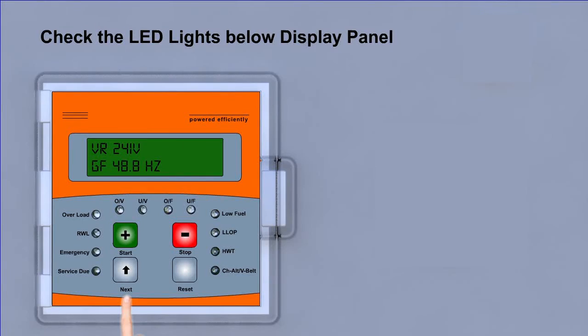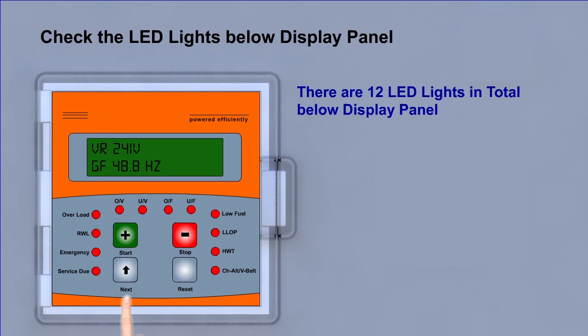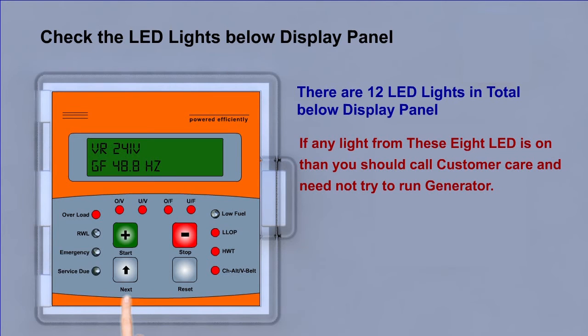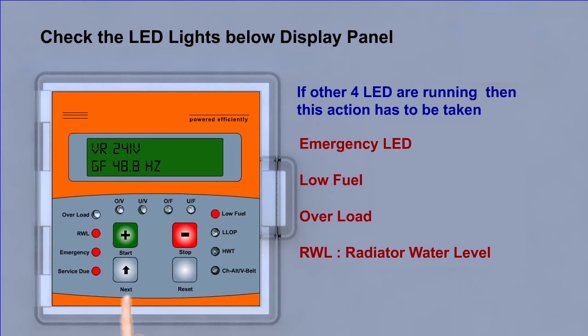Starting the generator, but it is not getting started. Number 1: Check the LED lights below display panel. There are 12 LED lights in total below display panel. If any light from these 8 LEDs is on, then you should call customer care and need not try to run generator. If other 4 LEDs are running, then these actions have to be taken.